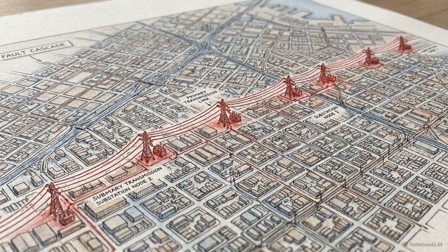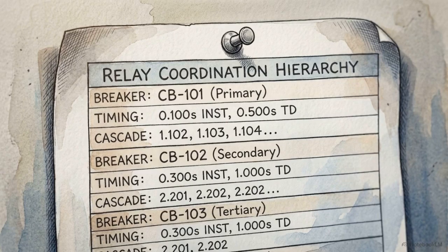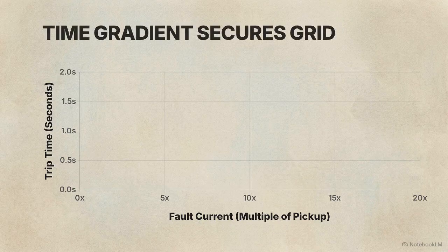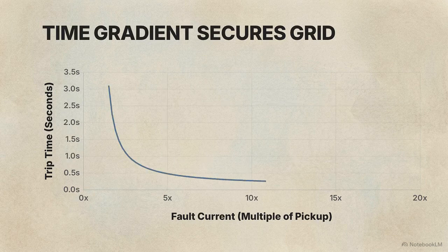Establishing the trip threshold only solves the first half of the problem. A single fault will send high current through multiple relays across the grid. To prevent the entire network from blacking out, these relays must act in a strict time-based hierarchy. This time-current coordination graph illustrates the logic of an inverse time overcurrent relay. The relationship is strictly inversely proportional. The larger the incoming fault current on the x-axis, the faster the relay trips on the y-axis.